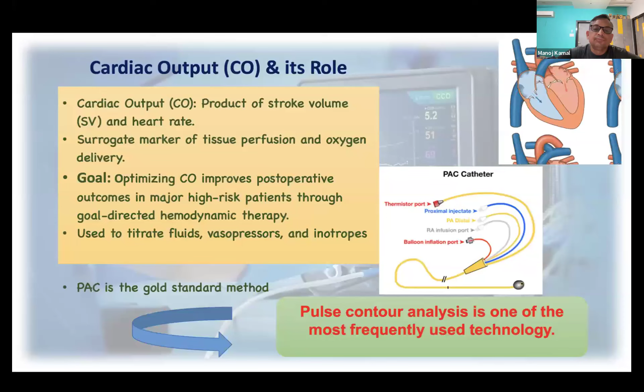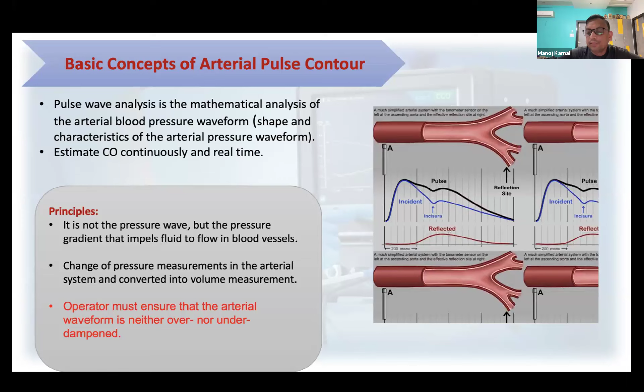As we all know, the basic concept of arterial pulse contour or pulse wave analysis is the mathematical analysis of the arterial blood pressure waveform, and it estimates cardiac output continuously in real time. It is the pressure difference, the pressure gradient, that impels fluid to flow in the blood vessel. By measuring the pressure difference at two levels, we convert this pressure difference into a volume measurement, so the operator must ensure that the arterial waveform is neither overdamped nor underdamped for arterial pulse contour analysis. The arterial pressure waveform is a complex physiological signal, an interplay between stroke volume, SVR, vascular compliance, and wave reflectance phenomena.